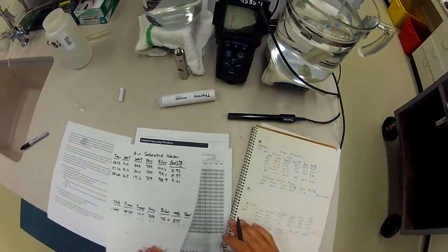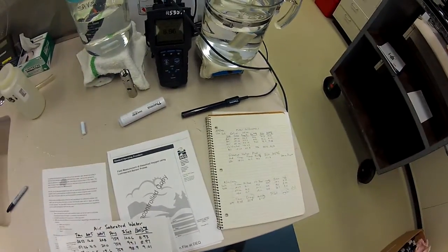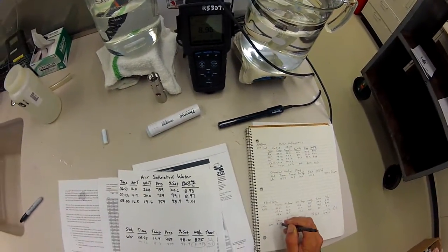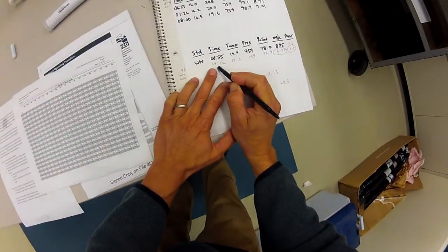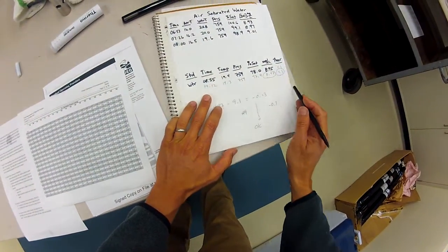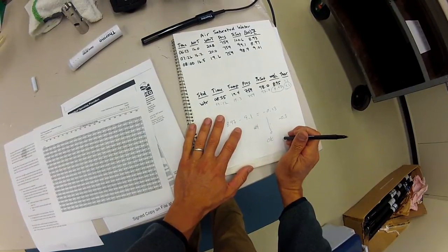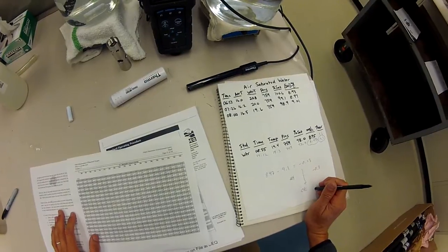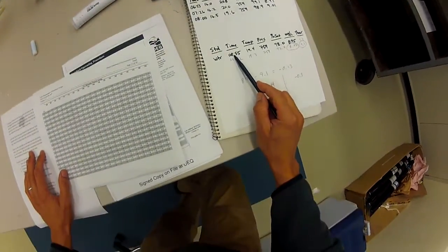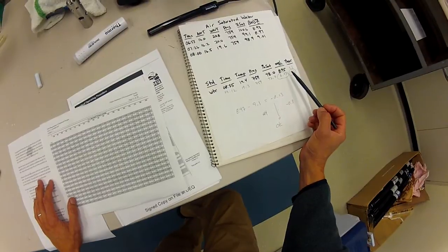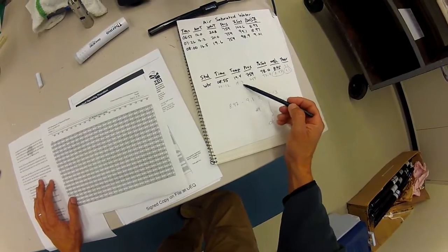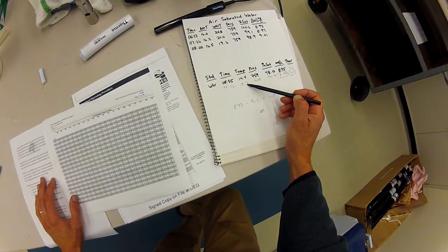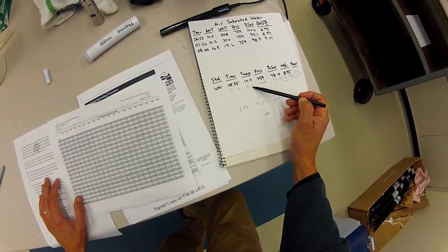On our field sheet, we would want to record the meter number, the time that we did our accuracy check, all of this information. And we would circle yes for the fact that we passed our verification criteria. We've recorded two times here to document that we have a reasonably stable standard. They're within a tenth for both milligrams per liter and temperature. That's what we want to have documented so that we know that our standard is reasonably stable.